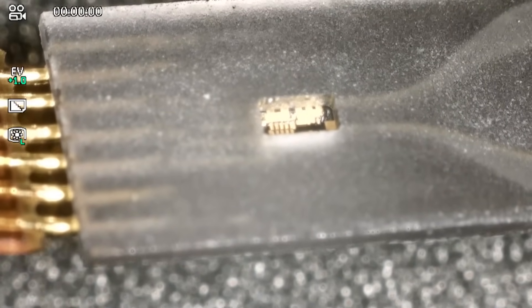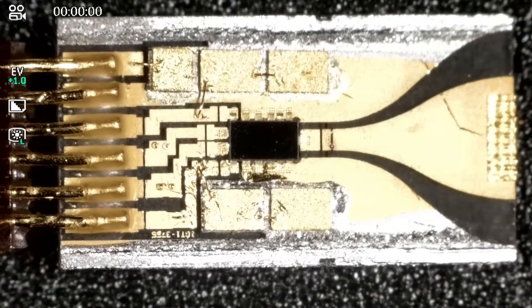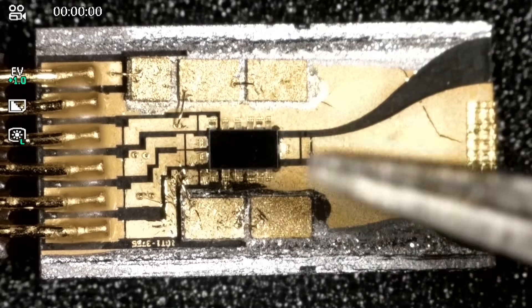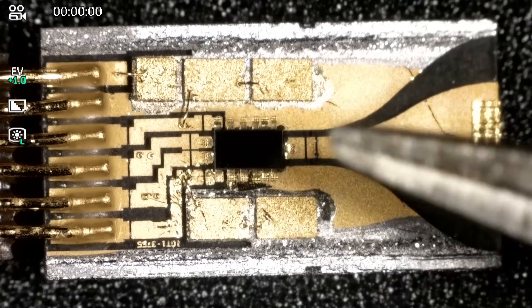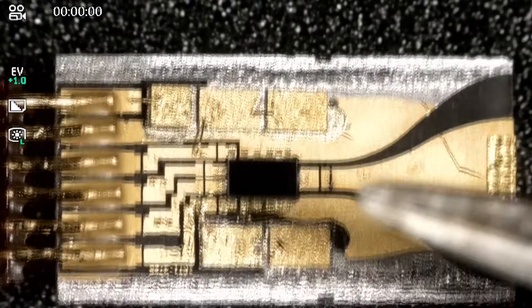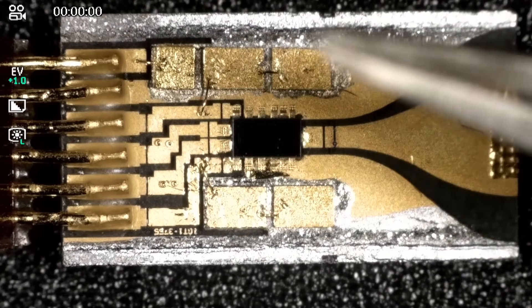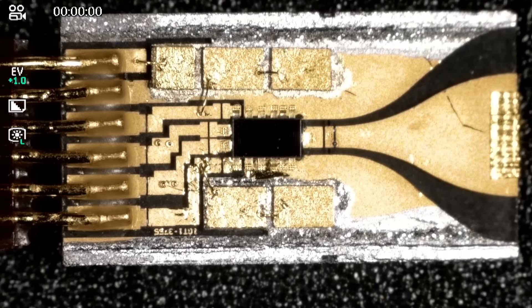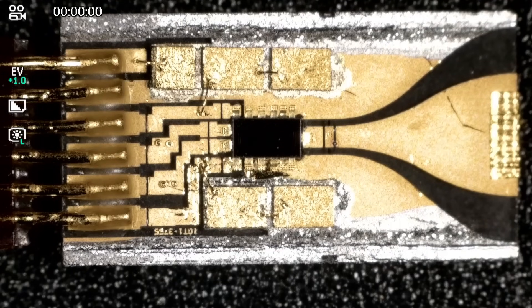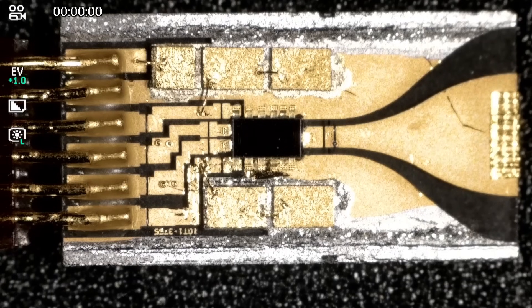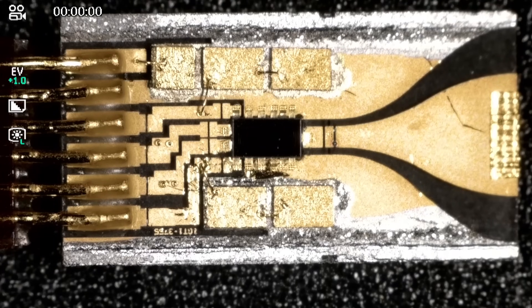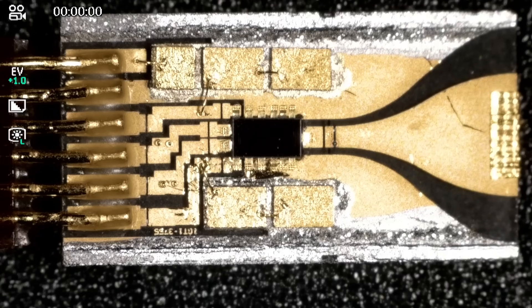This is the direct look at the IC on the other side. We should be able to take a look at the diodes more carefully. If I tilt it in a more extreme angle, you can see indeed there is a cutout there. Quite interesting. You can see that substrate as well. Very neat. Everything we said about how this is put together still holds. We can see our ground-signal-ground transition into coplanar from this coaxial input. There's some tiny thin film resistors there, probably some matching or interface to this chip to make sure it's properly terminated, and the capacitors on the surface. All custom made for individual purposes. The fact they're using this expensive substrate tells me they're probably using the same thing across all their high frequency detectors, the 28 GHz, 16 GHz, and maybe even 40 GHz versions.